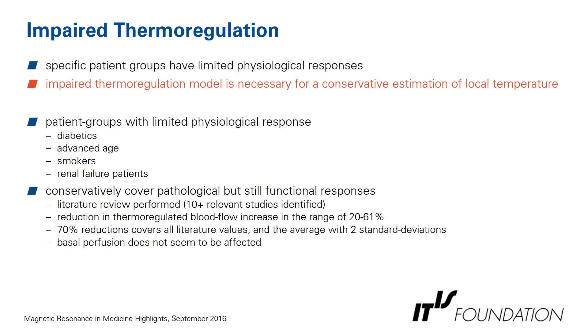An impaired thermoregulation model is necessary for a conservative estimation of local temperature for specific patient groups with limited physiological responses. These include diabetics, advanced age patients, smokers, and renal failure patients. We performed a literature review and concluded that a 70% reduction of normal response covers all literature values as well as the average with two standard deviations.